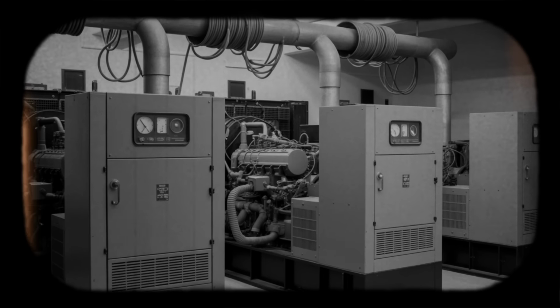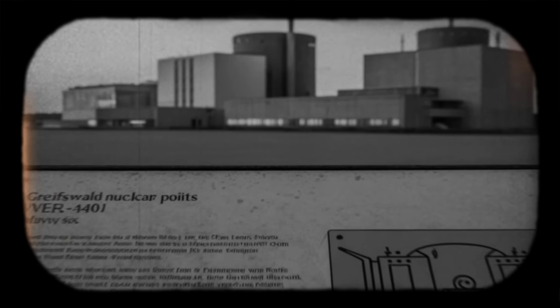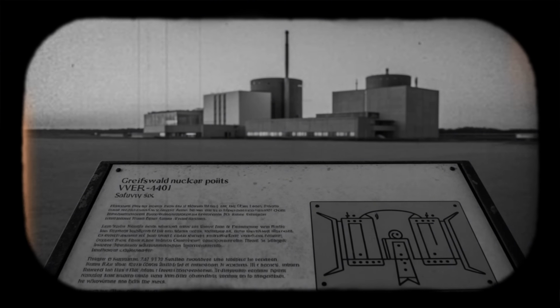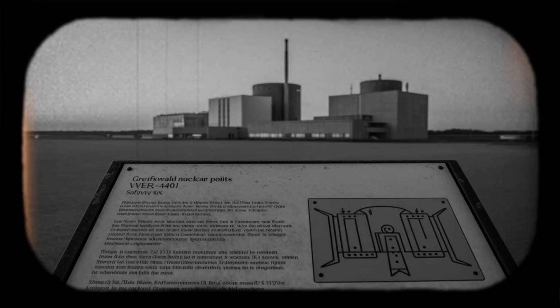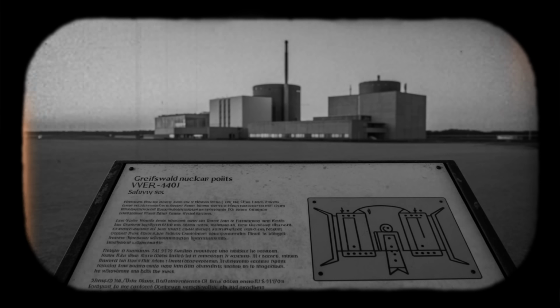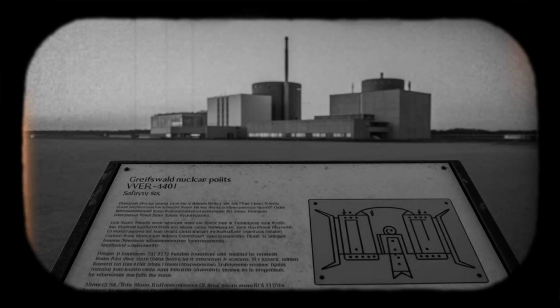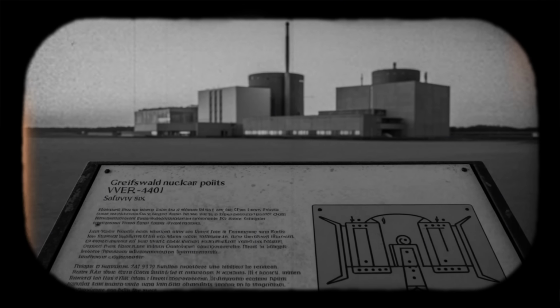The turbine hall stretched roughly 1,000 meters in length, according to East German analyses. Most of this volume lacked automatic fire detection or fixed suppression systems. Manual firefighting became the only defense, and manual firefighting takes time. Smoke, heat, and constrained access limited the brigade's effectiveness despite adequate staffing. Later international fire risk studies would return to this configuration repeatedly. The OECD and IAEA used Greifswald as a teaching example. How cable ducts, when inadequately protected and segregated, can transform from benign infrastructure into single points of failure. How turbine hall fires, starting in equipment considered non-nuclear, can propagate into safety-significant systems through shared routing.